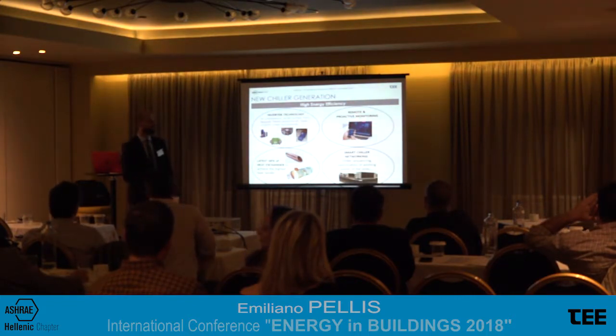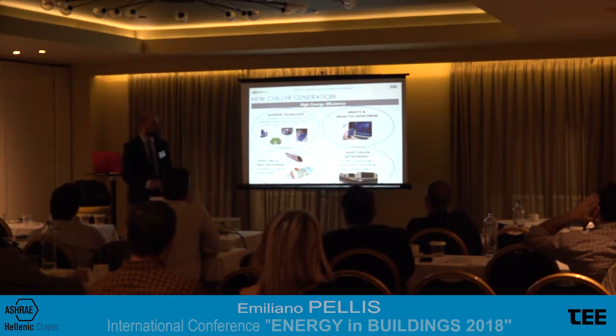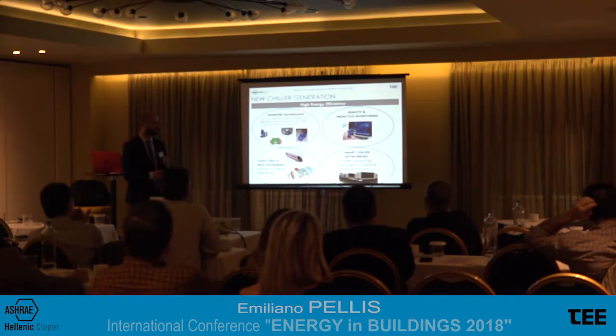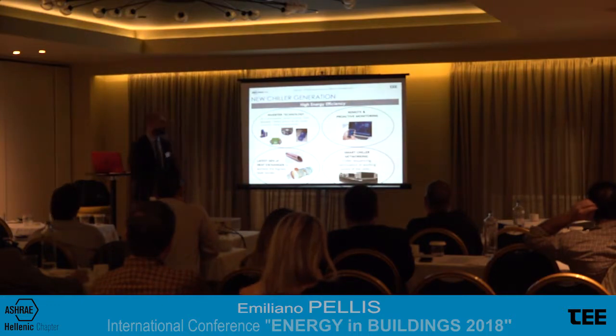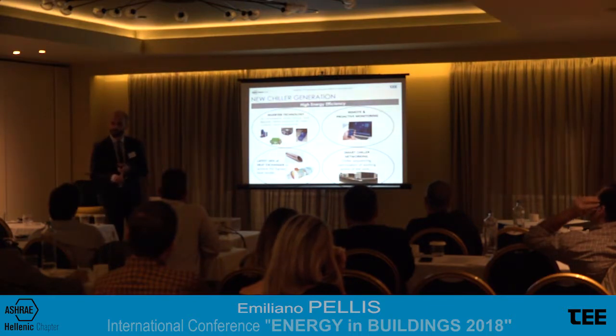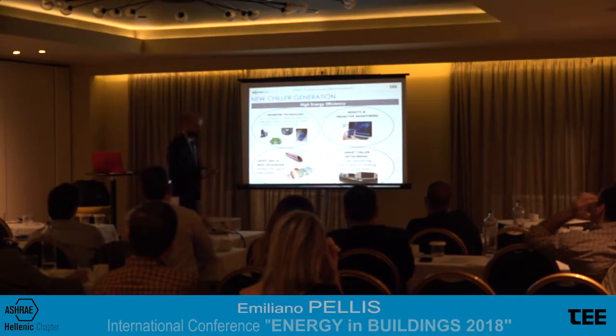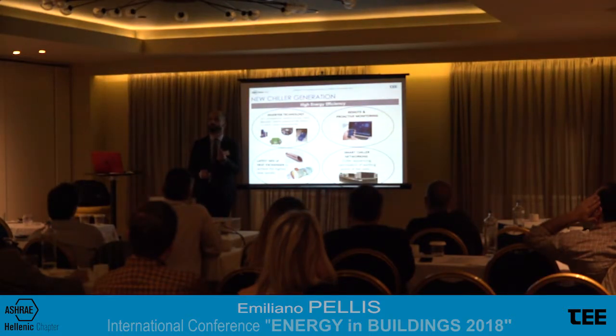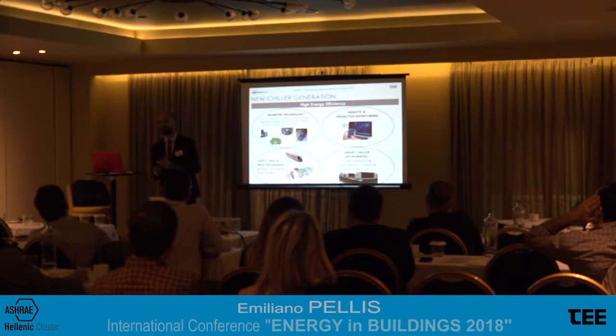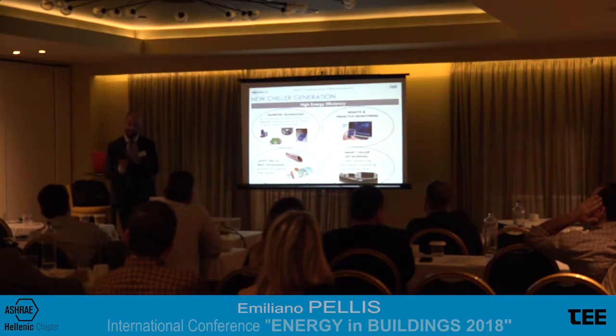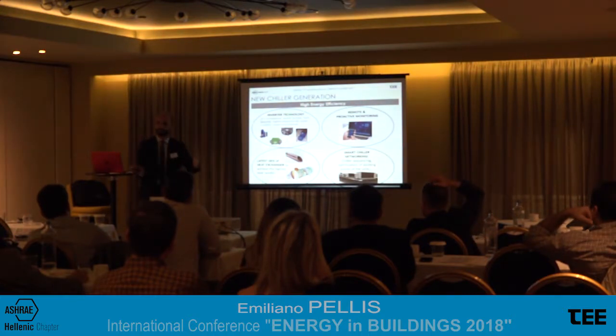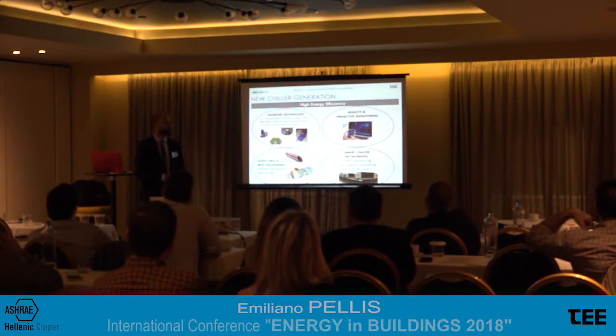So, remote and proactive monitoring, and finally, a smart control of chiller networking in case of plants with multiple units. So we need, for example, to introduce a proper chiller sequencing in order to optimize the number of operating hours, to have a good distribution, and to optimize the working point of the unit based on the peak of efficiency. To give a very practical example, a screw compressor typically has the peak of efficiency around 75–80% of its full load. So it is good that we take this into account when implementing the logic on the plant management. All of this to achieve high energy efficiency.